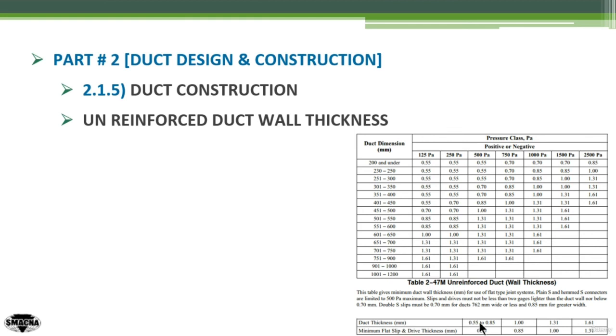For a duct thickness of 0.55 to 0.85 mm, use a joint thickness of 0.7 mm. For a duct thickness of 1.0 mm, use a joint thickness of 0.85 mm. For a duct thickness of 1.31 mm, use a joint thickness of 1.0 mm. For 1.61 mm duct thickness, use a minimum flat slip and drive thickness of 1.31 mm. This is how to specify the thickness of the unreinforced duct wall.